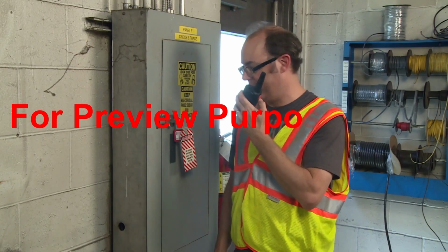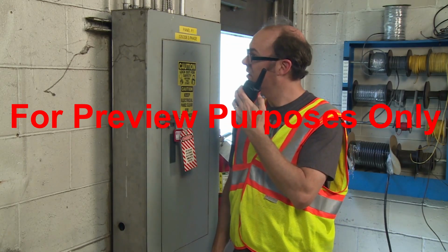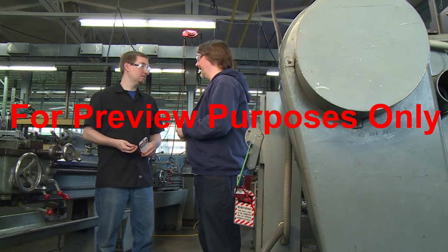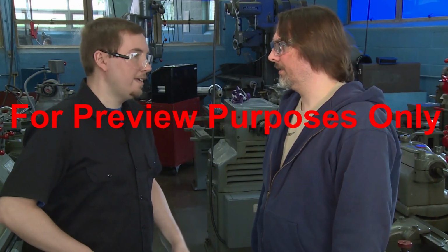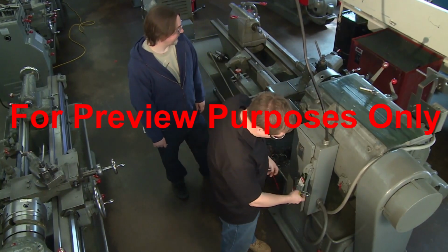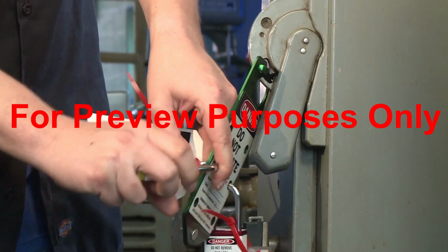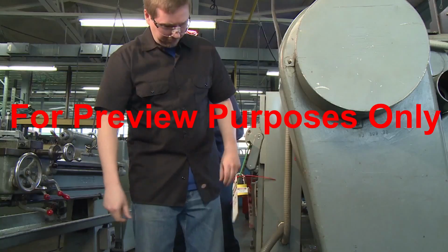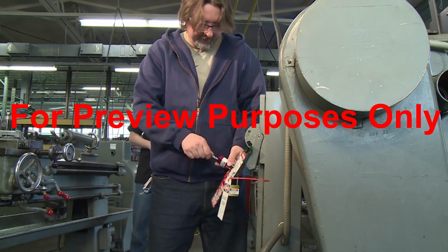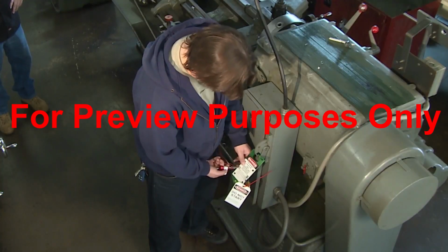In some special situations, additional procedures must be followed when locking and tagging out a machine. One of the most important of these occurs if you have a personnel change during the time the equipment is being serviced. In these situations, it is important to maintain continuity of responsibility. First, personnel from the new incoming work shift must install their lockout tagout devices. Then, the locks and tags that were installed by the departing work shift should be removed.